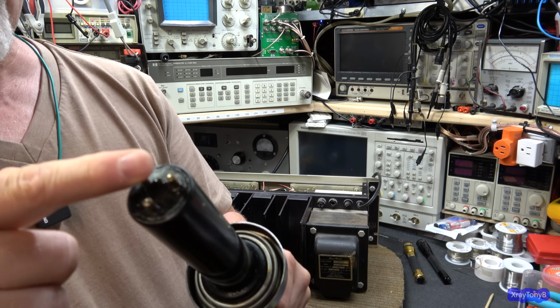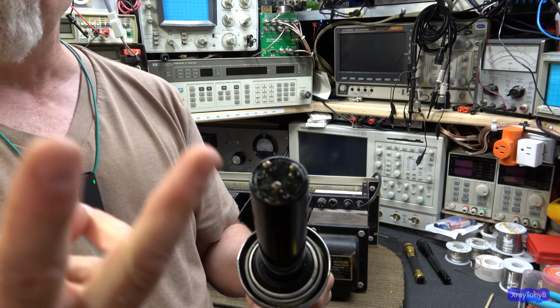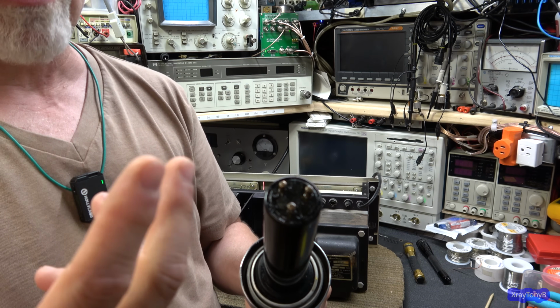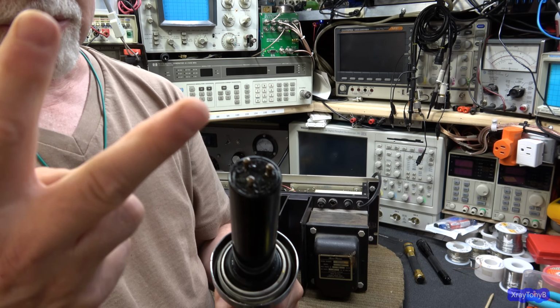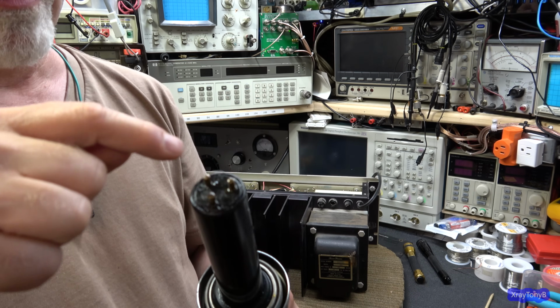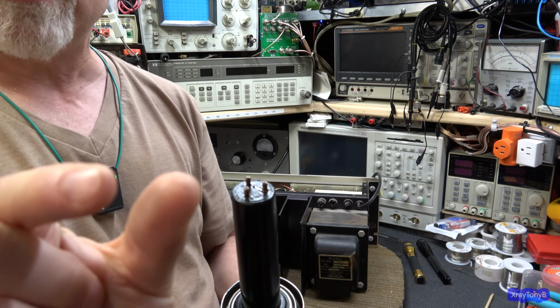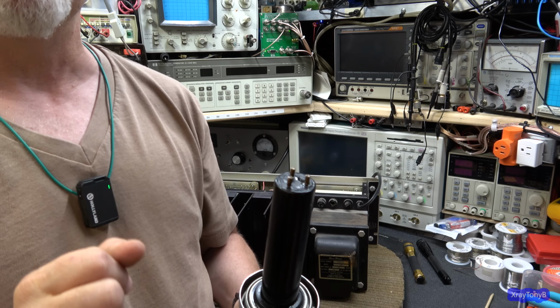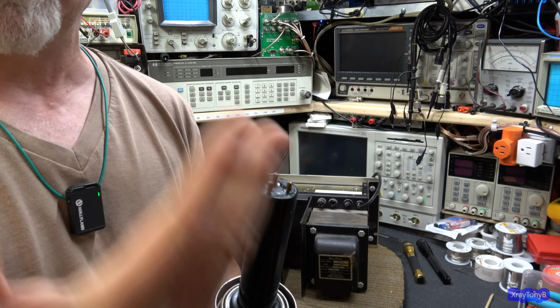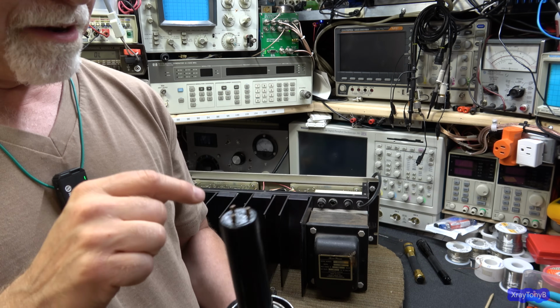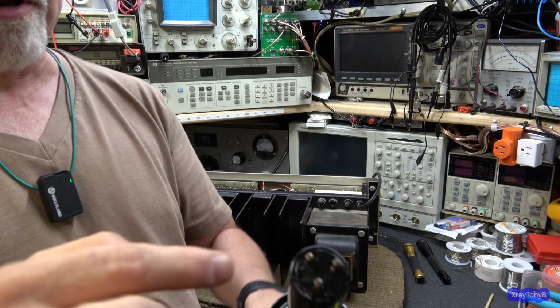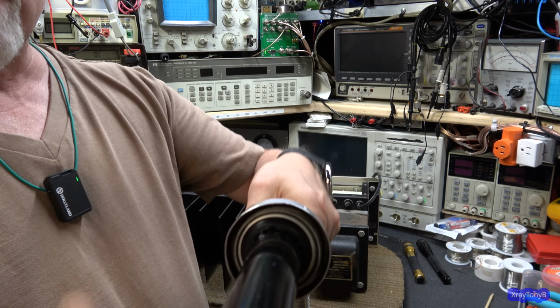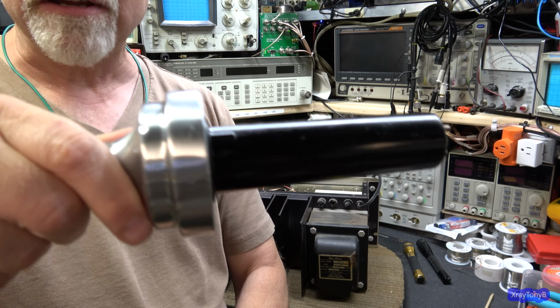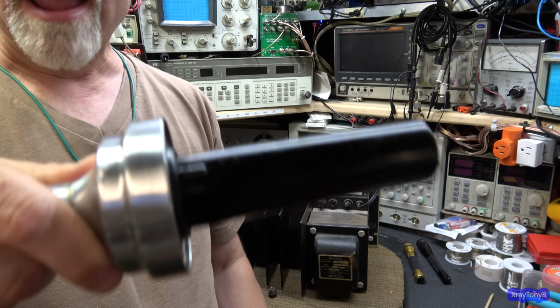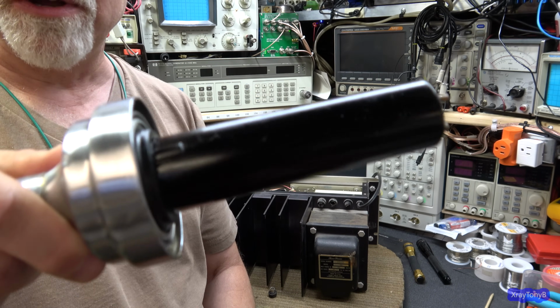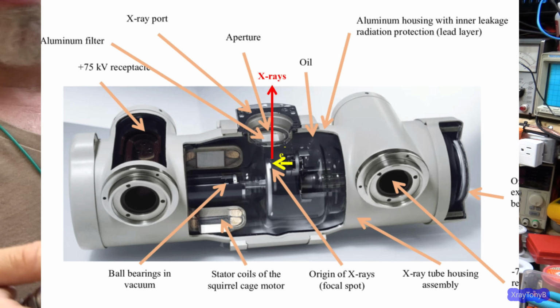And the reason there's 3 pins is because an X-ray tube has 2 filaments in it. Unlike a normal vacuum tube, it has 2 filaments. So you have a smaller sized filament, a larger sized filament, and guess what? They're called the small filament and the large filament. And then there's a common. They're both connected to the common. And that's what these 3 pins are. This plugs down into the X-ray tube housing, and this provides 1/2 of the power for the tube, because there's 2 of these. One on the anode side and one on the cathode side.